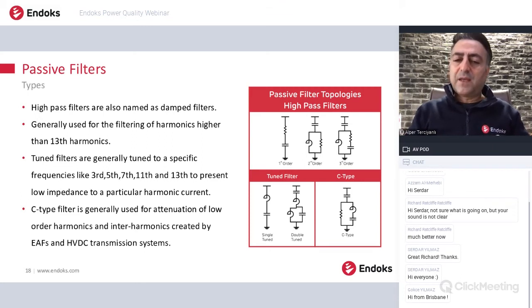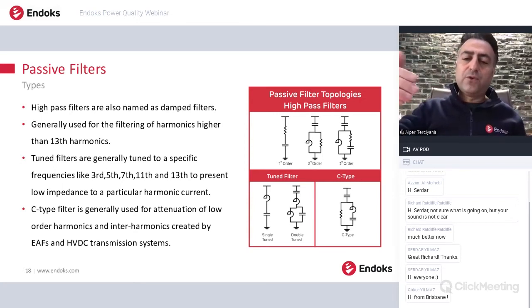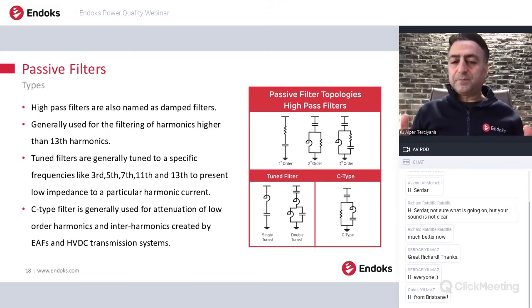What does that mean? It means that the impedance of the filter at that specific frequency is ideally zero. So if you inject a 250 hertz current from the load side, since this impedance is ideally zero, this current does not flow to the grid, but flows through the filter circuit. This is the main idea of the filters.